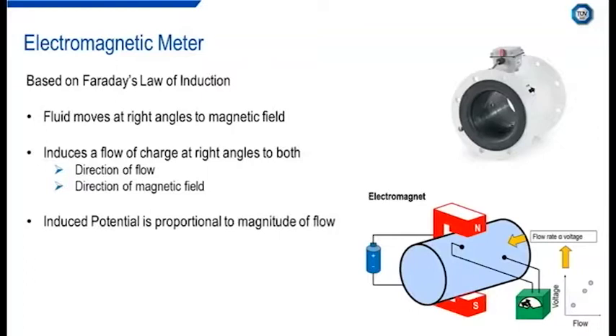The electromagnetic meter, commonly known as the mag meter, is an example of a volumetric flow meter which doesn't have any mechanically moving parts and is ideal for wastewater applications. Mag meters are also ideal for applications where low pressure drop and low maintenance are required, as long as the liquid is conducting, as the operation of an electromagnetic flow meter is based upon Faraday's law of induction, which states that the voltage induced across any conductor as it moves at right angles through a magnetic field is proportional to the velocity of that conductor.